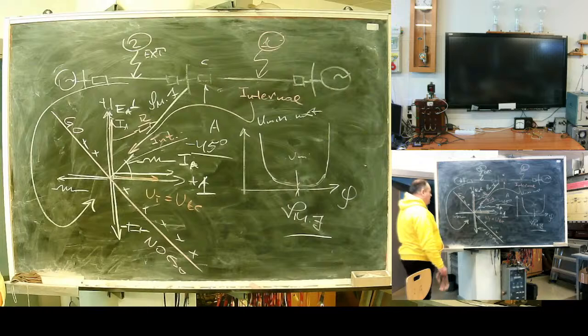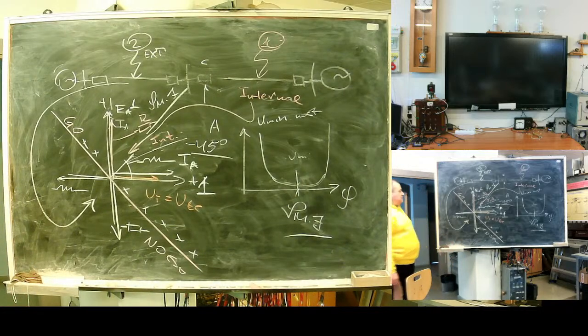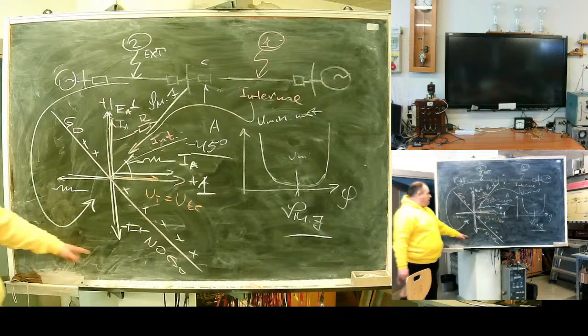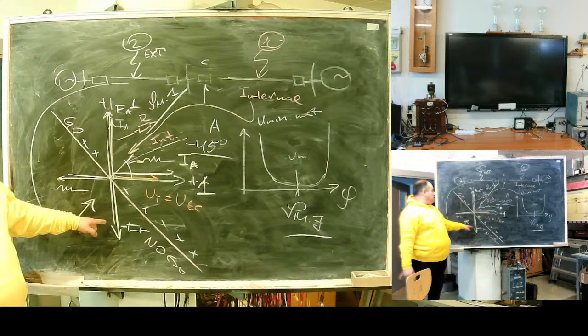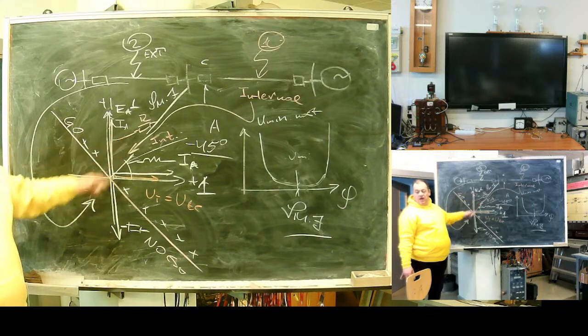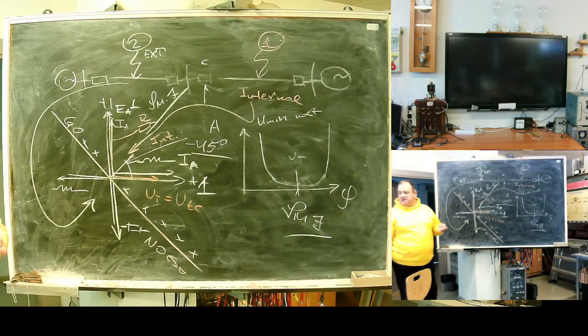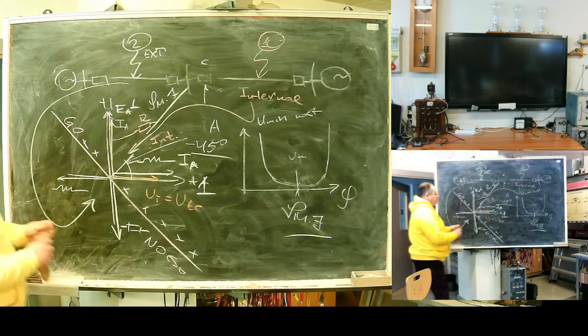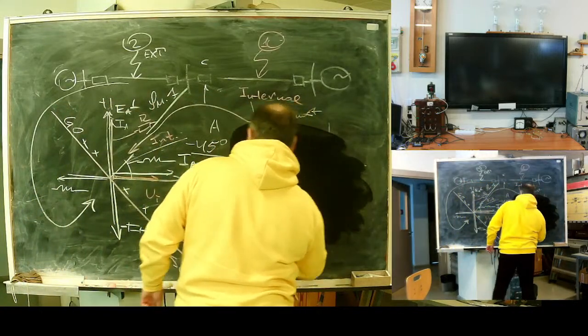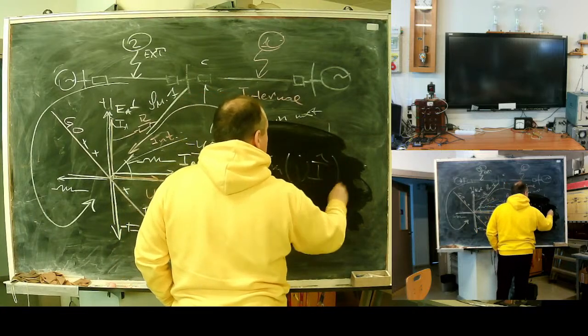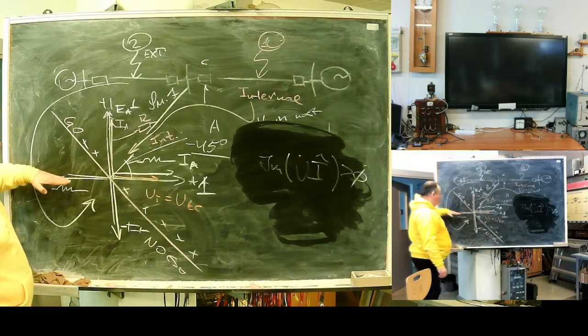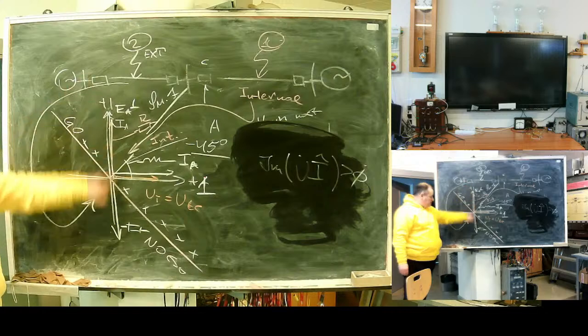I can try a different kind of relay. If I try pure active, I will have this vertical line. This means I do not operate in case of cable fault. What can I also try? I can try not an active power meter, but reactive. I can try a relay with imaginary part greater than 0. It will give me a characteristic like this, also not the worst one. Possible false trip, also with this kind, may cause false trip.